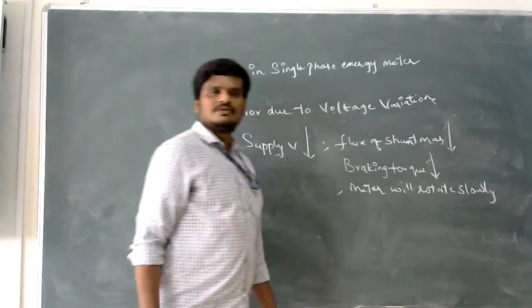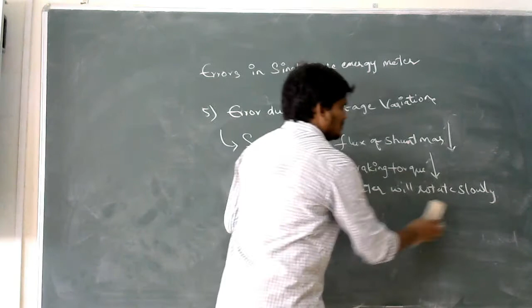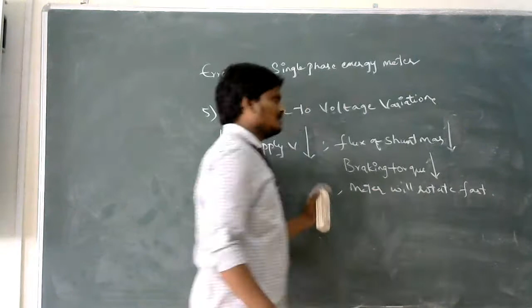Suppose if the supply voltage decreases, what happens to the flux of a shunt magnet? Decreases. Due to that, the production of braking torque will also decrease. What happens? The meter will rotate very fast. So, if I increase or decrease the supply voltage, it will have an effect directly on the braking torque. So, we need to compensate the errors which are caused due to the voltage variations.